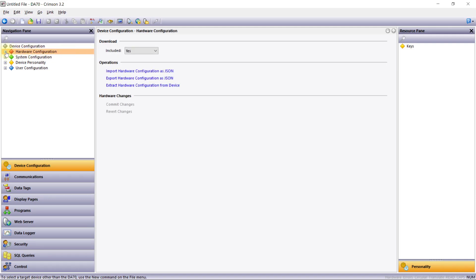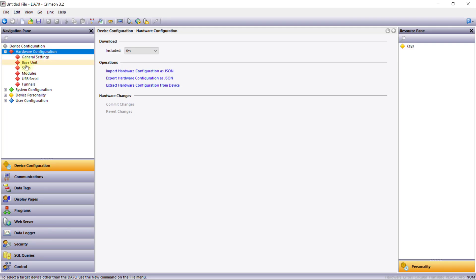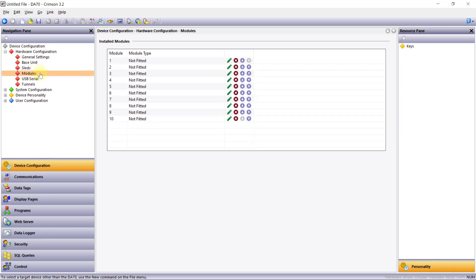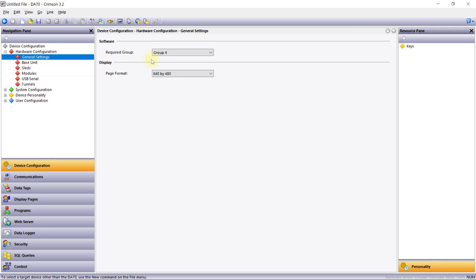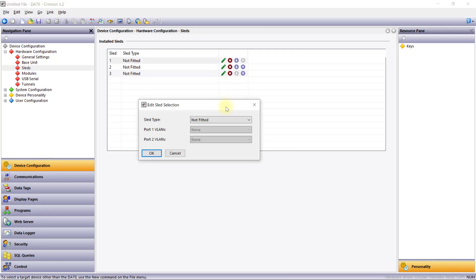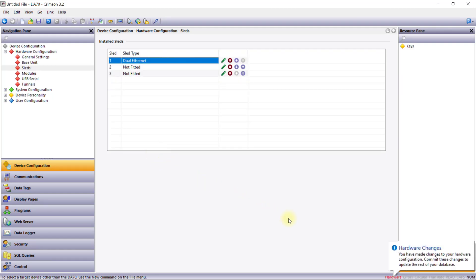The Hardware Configuration section is used to select the hardware options installed in the device. For a FlexEdge device, this includes specifying which sleds are installed, and for a DA70, which I/O modules are fitted. This section also defines global properties like the target software group, virtual HMI resolution, and the number of tunnel or VLAN interfaces. When you make any hardware configuration changes, you will be prompted to commit those changes to update the system configuration with the new interfaces and options. For example, when I add a dual Ethernet sled to my database, I receive this prompt to commit the change.